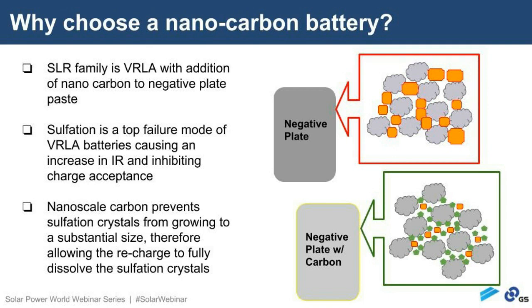Sulfation is a top failure mode of VRLA batteries, causing an increase in internal resistance and inhibiting charge acceptance. That all correlates back to the buildup of sulfation crystals over the life of the battery. The nanocarbon additive really mitigates that sulfation crystal problem altogether.